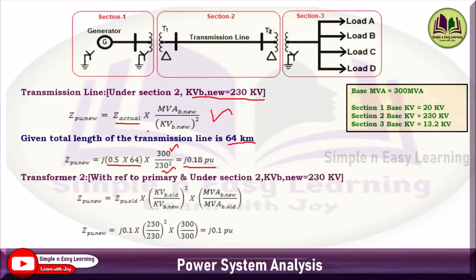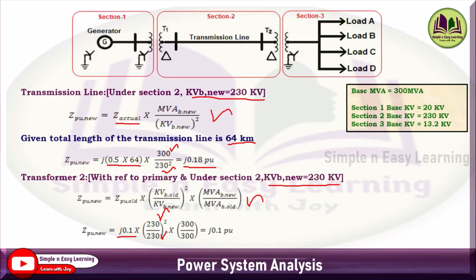For Transformer 2, consider with reference to the primary (HT side in Section 2, base kV = 230 kV). The impedance is given in per unit, so use the formula: Z_pu_new = Z_pu_old × (kVB_old/kVB_new)² × (MVA_B_new/MVA_B_old). Substituting j0.1 × (230/230)² × (300/300) = j0.1 pu.